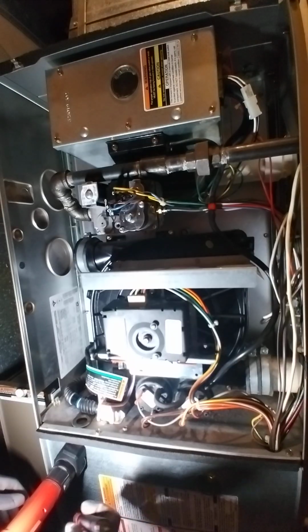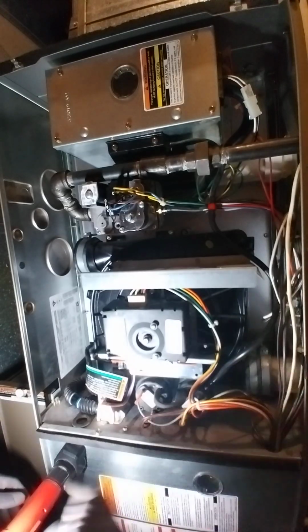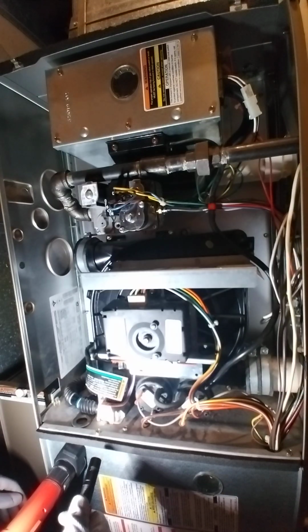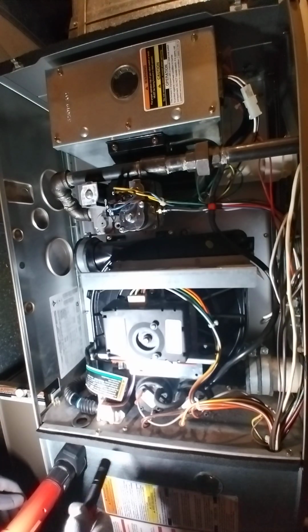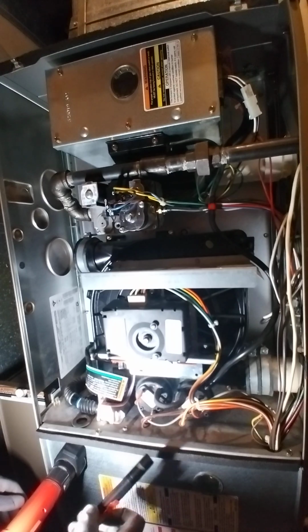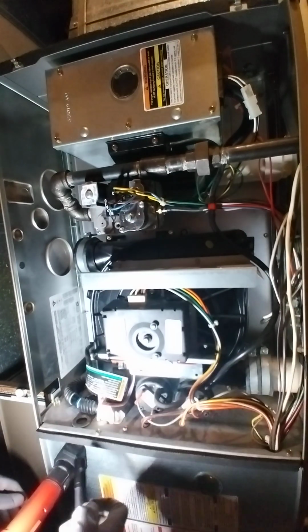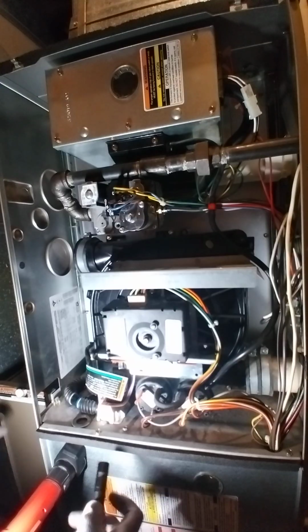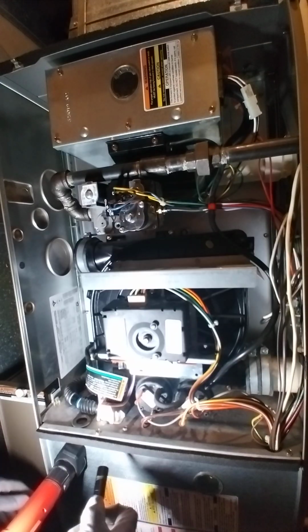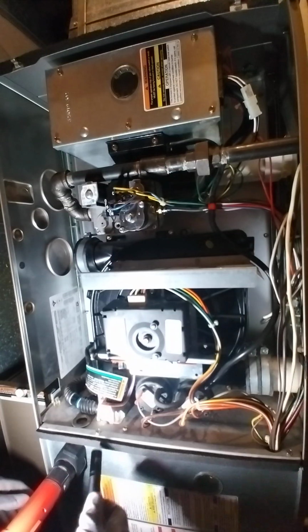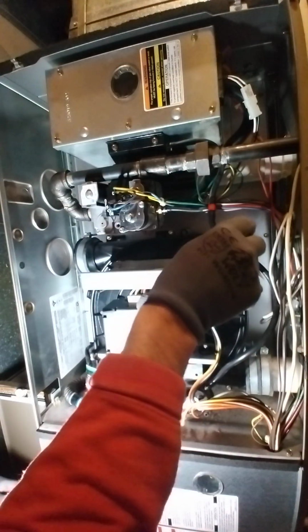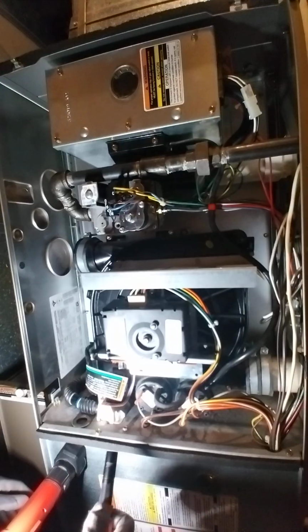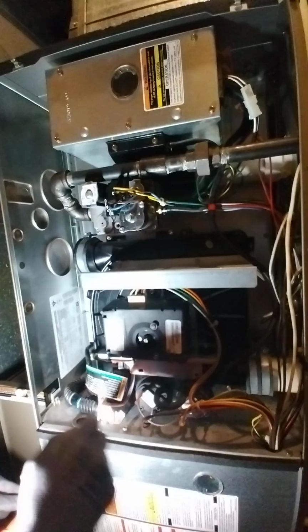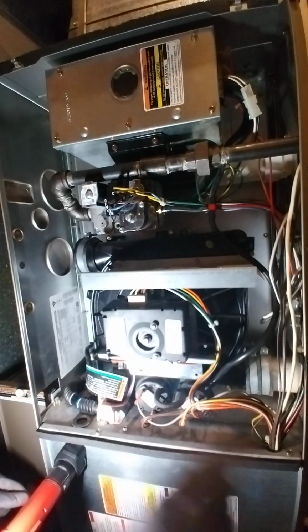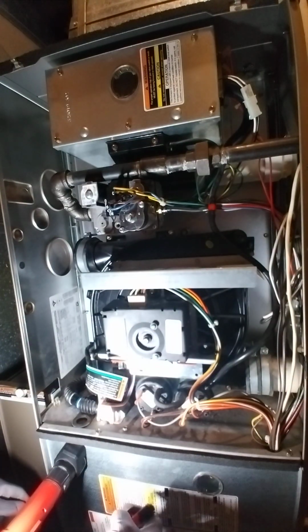So when I read those error codes and I remembered what had happened maintenance-wise to this thing, I looked through the manual, and sure enough, there's a mention about how when the furnace is first installed, before you can let it operate, you need to prime the condensate trap here. And there's a filler spout right here for doing that, so that you just pour a bunch of water into there, and eventually it drains through the tubes and into the condensate trap, and then out the actual drain itself.